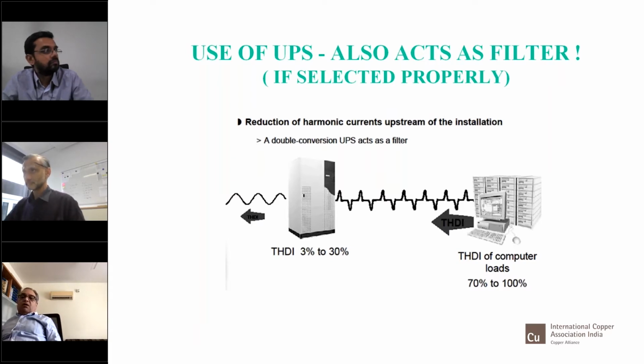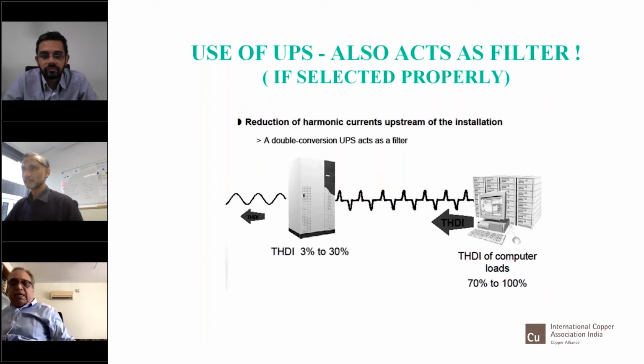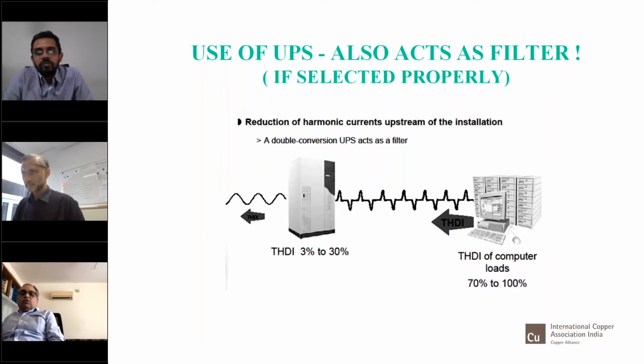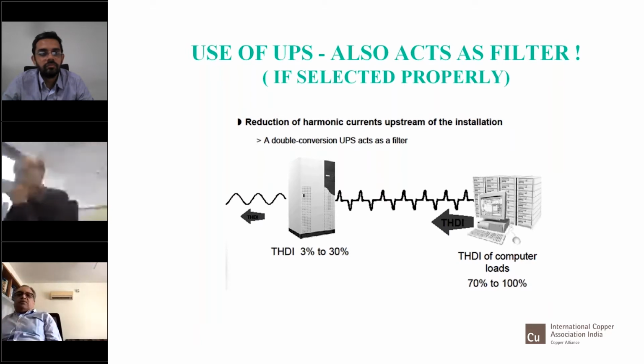But not long ago, 10 years ago, if you had not been careful, you would buy a UPS which is actually giving you 30% harmonics. And since the UPS is connected between the transformer and the computers, this UPS would give 30% harmonics, although from computers you get something like 70% harmonics or even more.